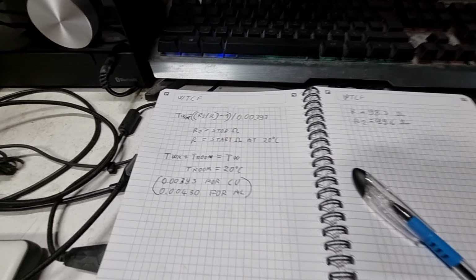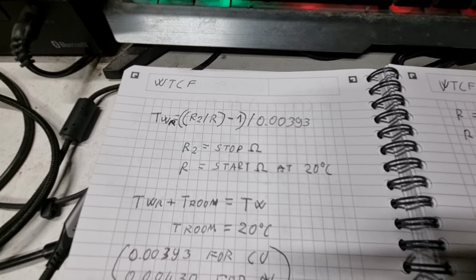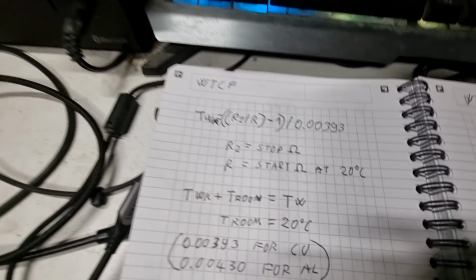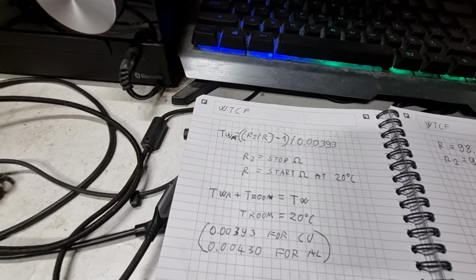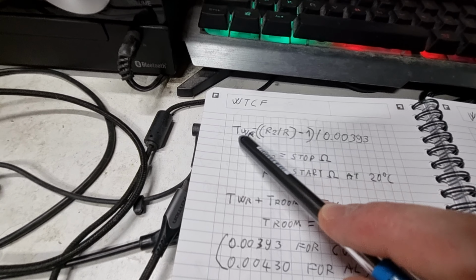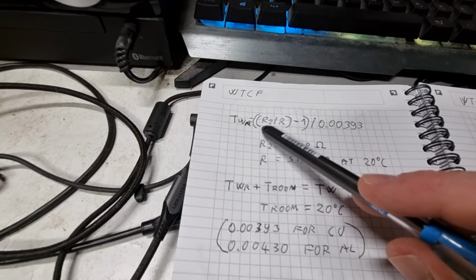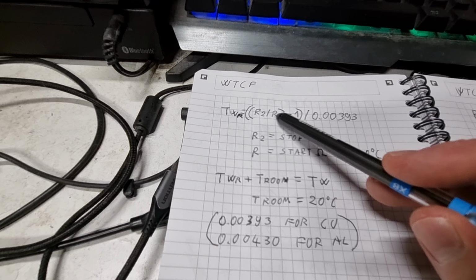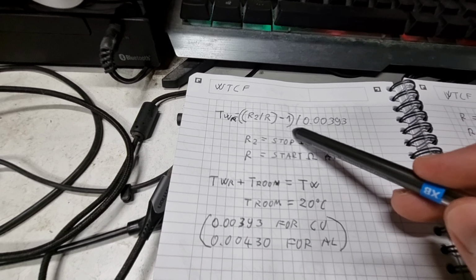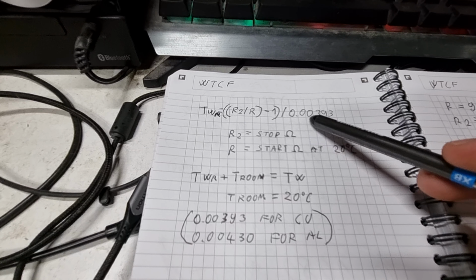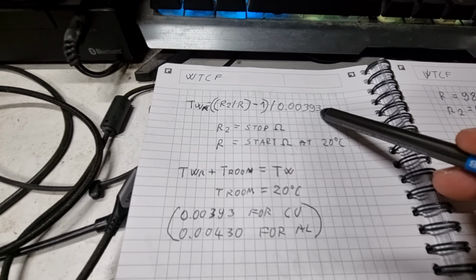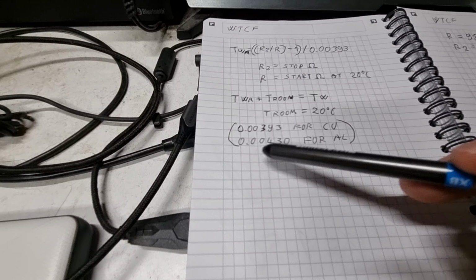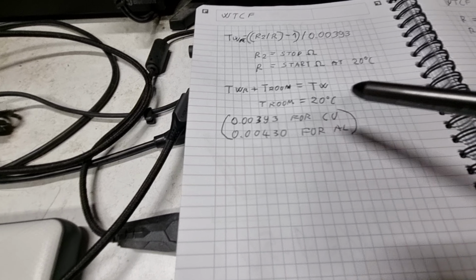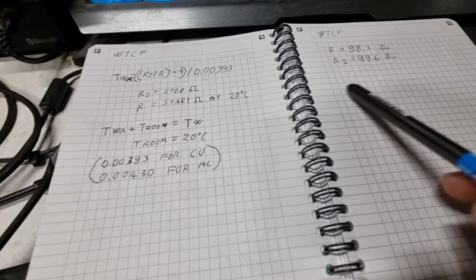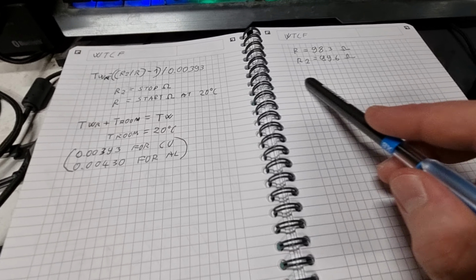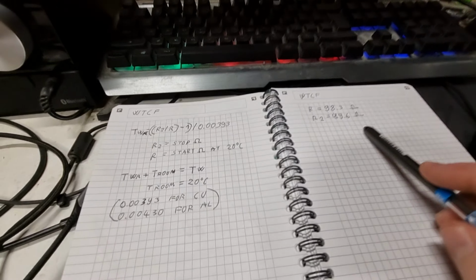Okay, we're back at the paper. Now we can use this formula: the winding temperature rise equals R2 divided by R1, minus 1, divided by 0.00393, which is the coefficient for copper. For aluminium it would be a different coefficient. I'll write this formula down and use the calculator, and be right back.